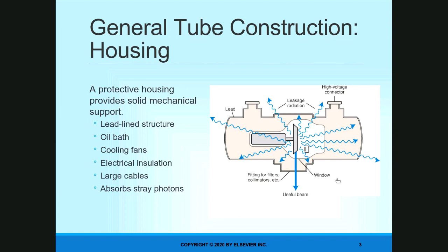So there is a certain amount of leakage that is acceptable, but it cannot exceed that, and the state actually comes in and tests that amount of leakage radiation, and if it exceeds that number, then the state would force you to shut down.